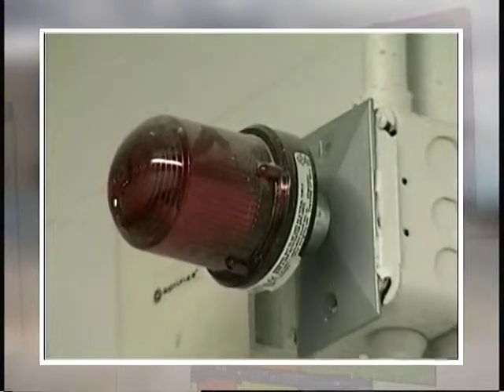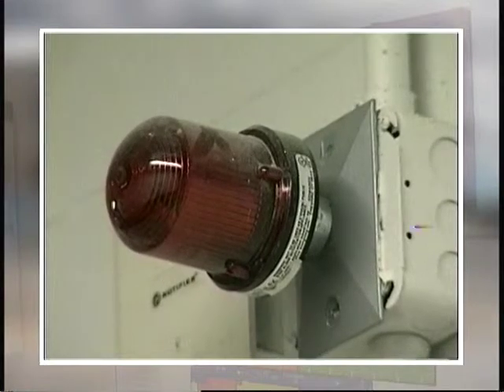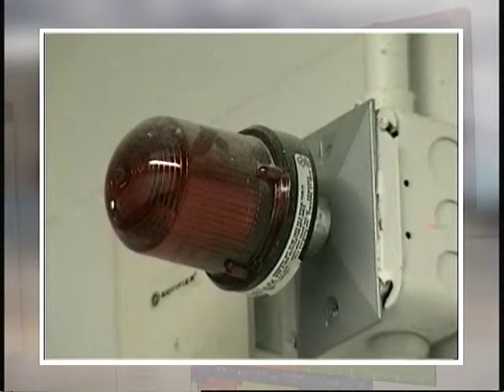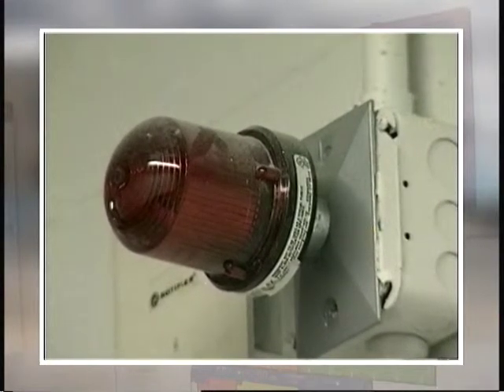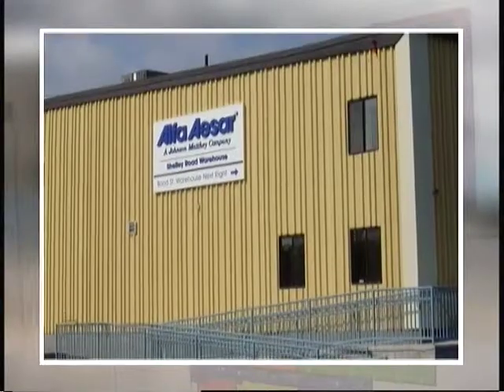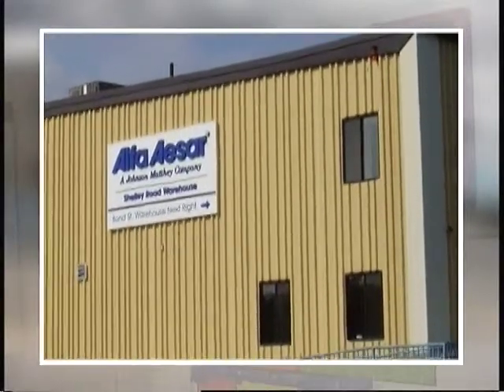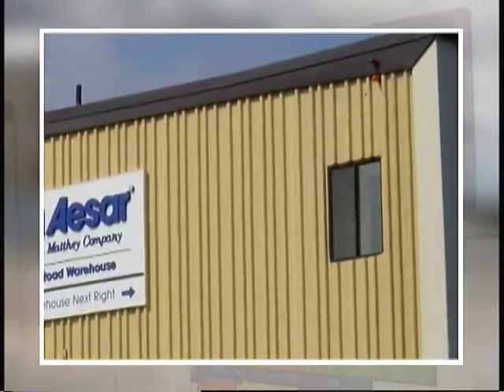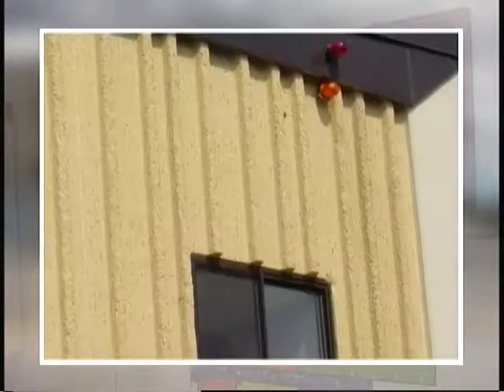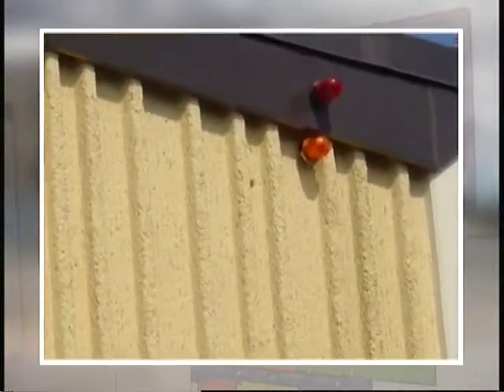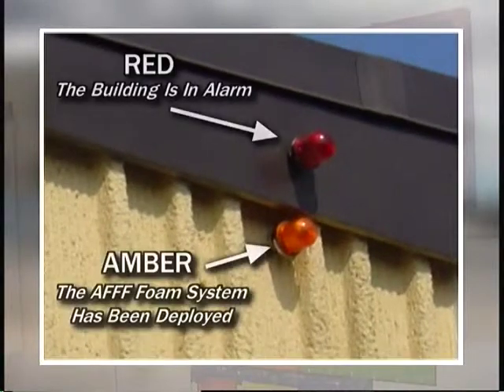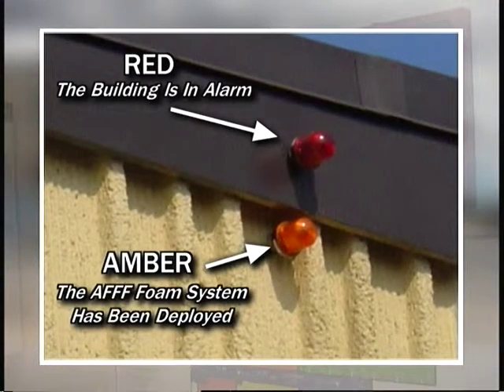Beacons are located outside of exterior and interior doors to each storage area in order to indicate which space is in alarm. 2 beacons are mounted on the front corner of the building where first responders can easily see them on approach to the scene. A red beacon indicates the building is in alarm. An amber beacon indicates the alarm is in the flammable liquids area and that the AFFF foam system has been deployed.